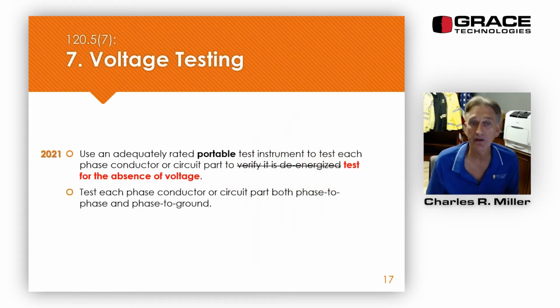All right, number 7, voltage testing. We are to use an adequately rated portable test instrument to test each phase conductor or circuit part. It used to say to verify it is de-energized. In the 2021 edition, the wording changed. We test each phase conductor or circuit part to test for the absence of voltage, because this is what is being done. We are testing that there is no voltage there.